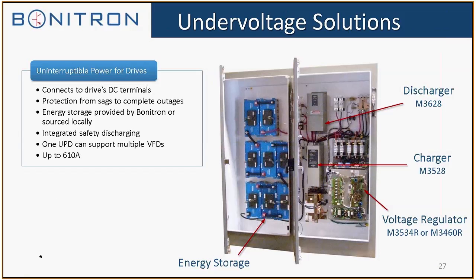This gives you a little more detail about the layout of a cabinet. This can help if you have your own integration capabilities. It connects to the drive's DC bus terminals, as all the ride-through does. And one UPD can support multiple drives. If you've got multiple drives in one cabinet, you can set a UPD rated for all of the drives, up to 610 amps in a single cabinet, and we can master-slave any of the ride-through solutions up to higher kilowatt ratings. Single unit, 250 kilowatts.